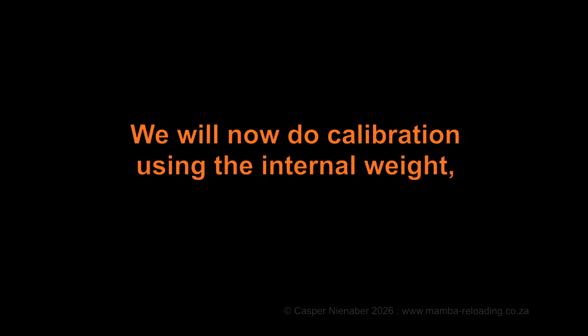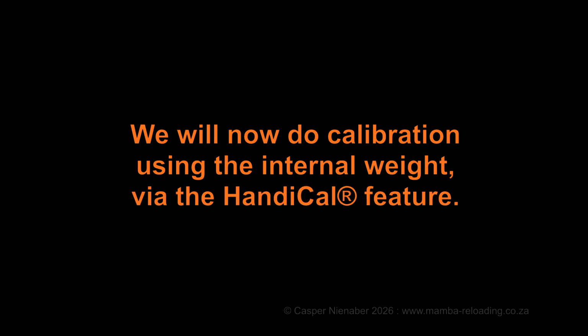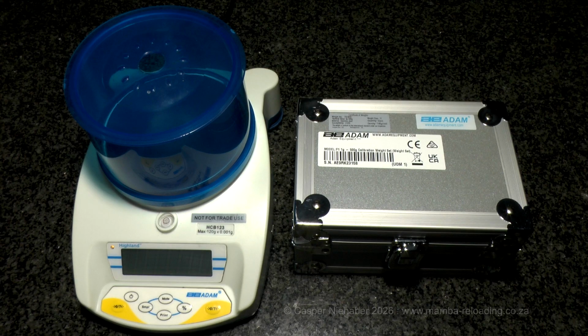We will now do calibration using the internal weight via the HandiCal feature. To enter the calibration menu, press the On button, then press and hold both the Sample, SMPL, and Print buttons simultaneously until Unload appears. Press the yellow Zero Tare button. The display will read C, INT, indicating calibration by using the internal weight via the HandiCal feature. Press the yellow Zero Tare button again. The display will read Load.